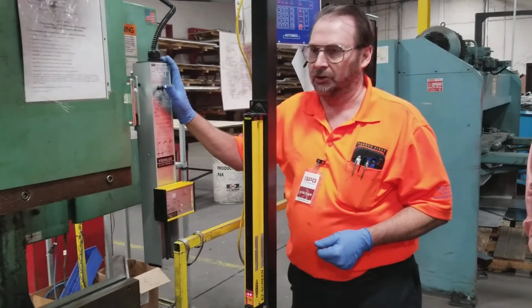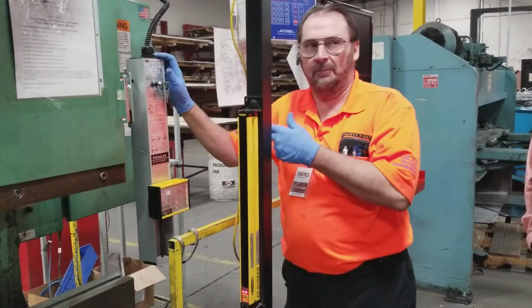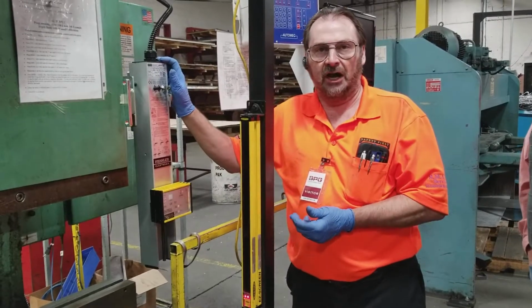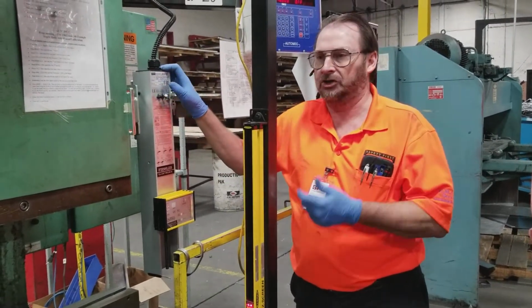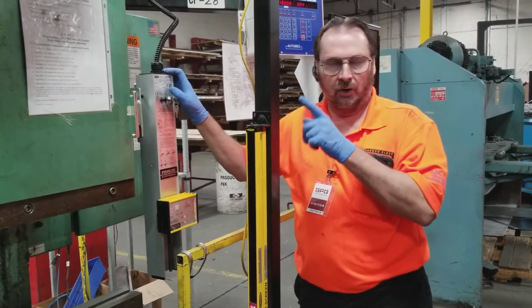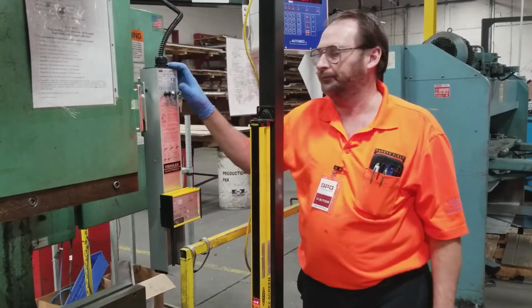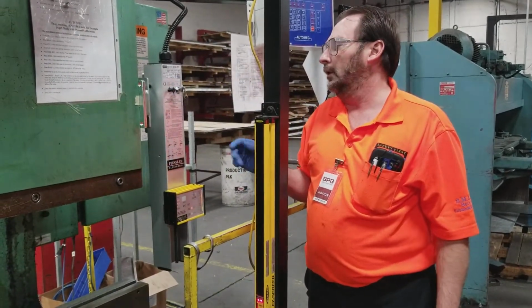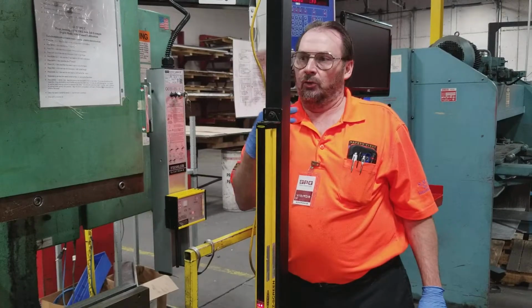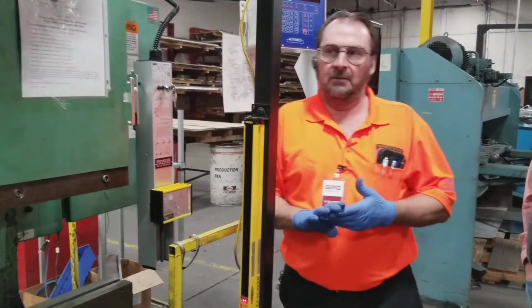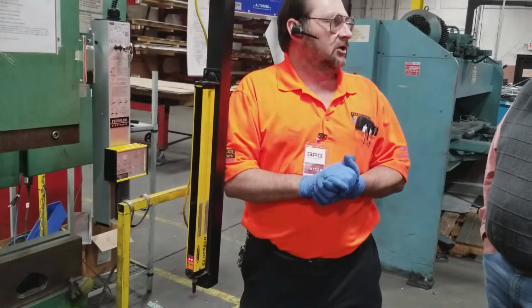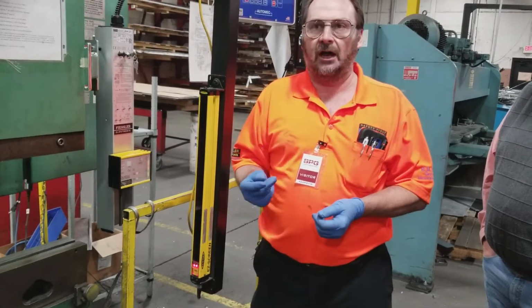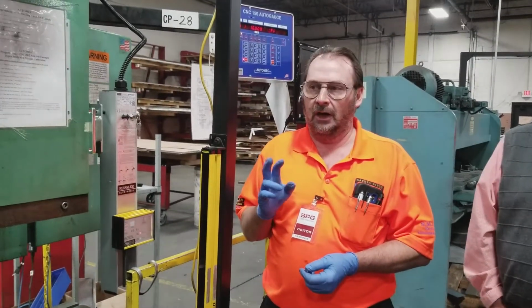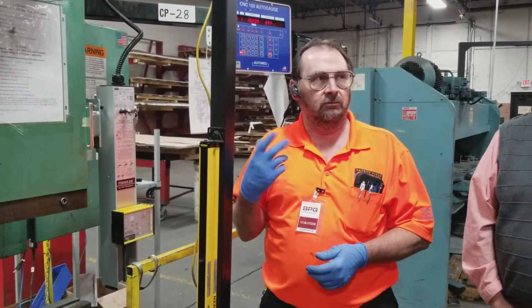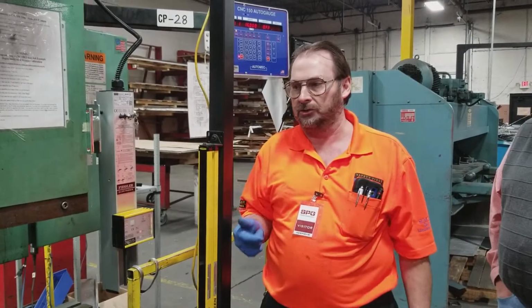The push button controls the receiver up and down and initiates calibration. The toggle switch confirms calibration and controls the transmitter up and down. The first three things that we're going over are alignment, calibration, and manual adjustment. We'll first do calibration, then we'll do manual adjustment, and then we'll go through the alignment procedure.